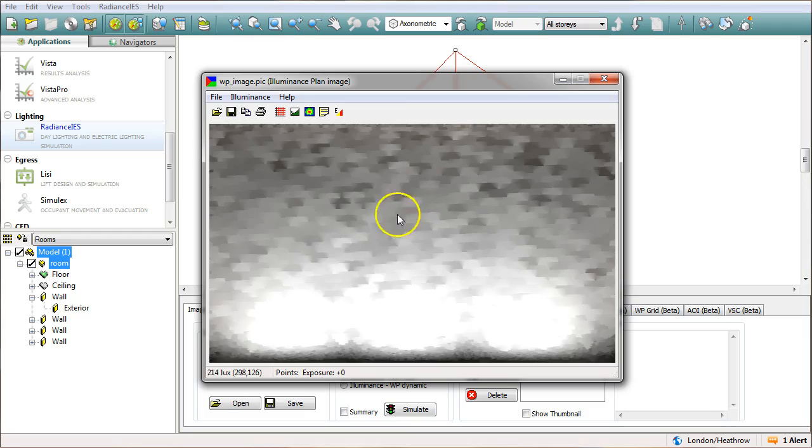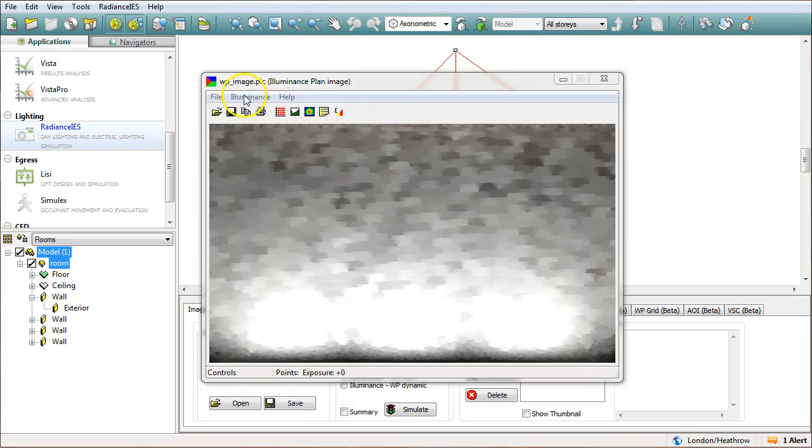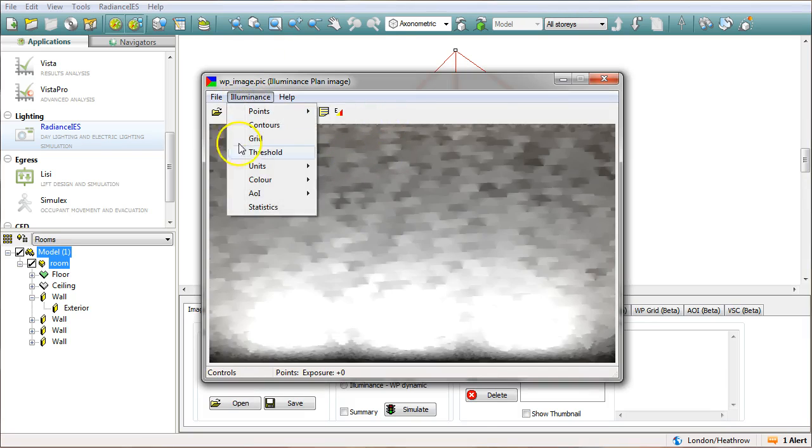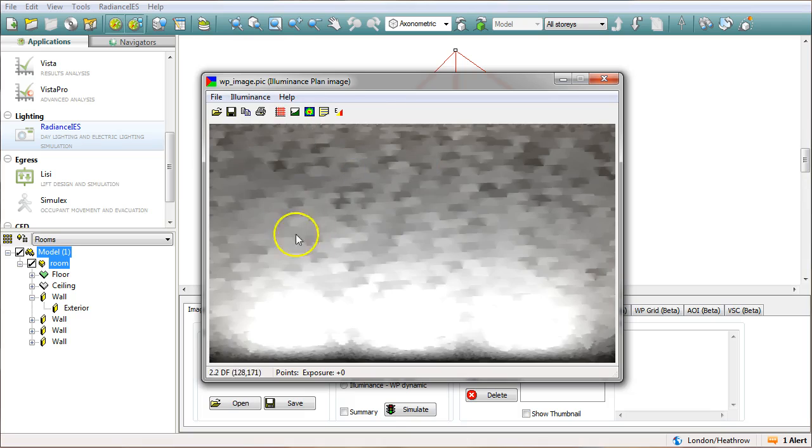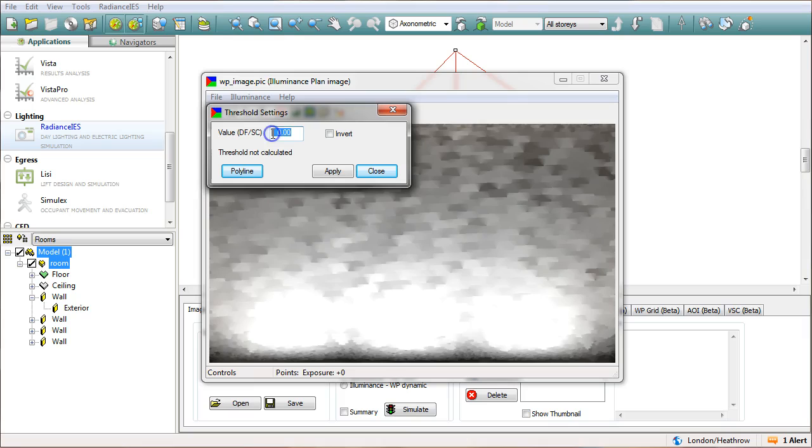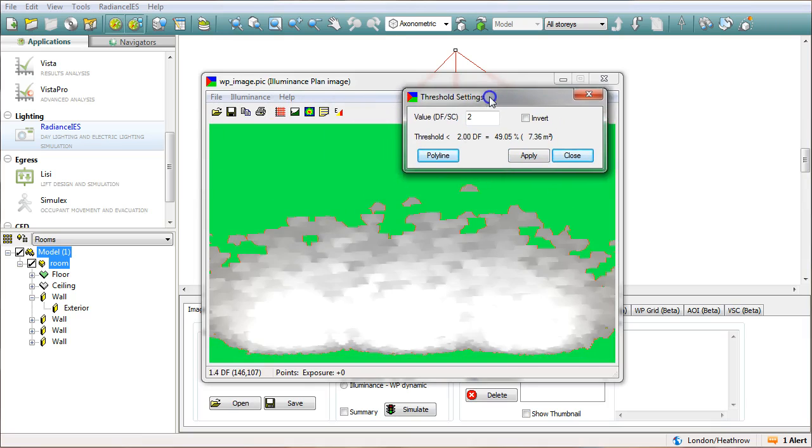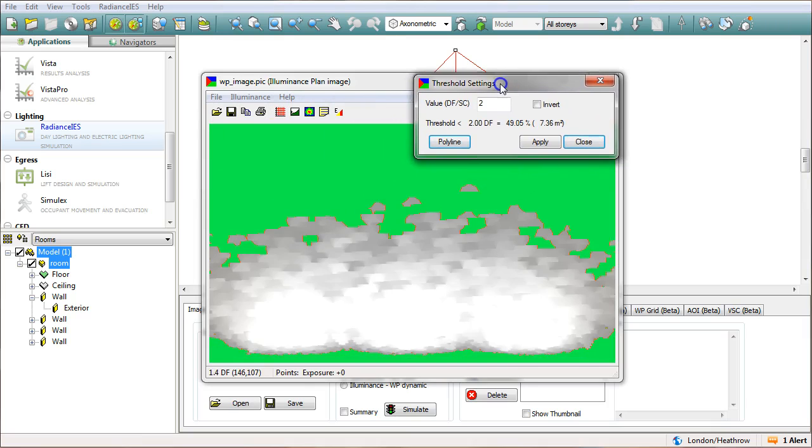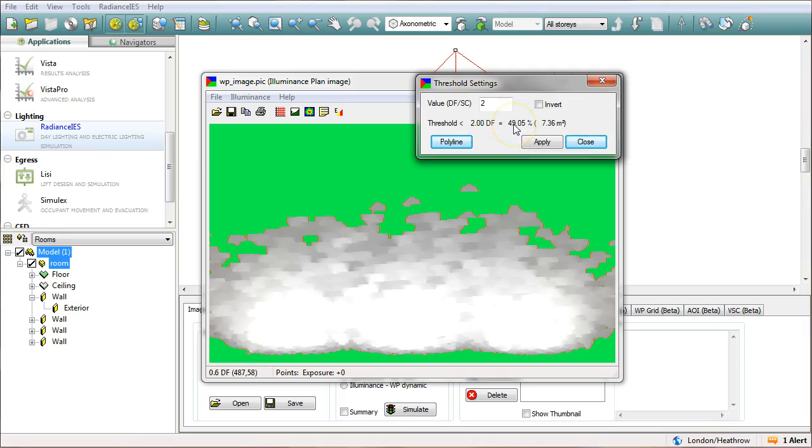Okay so here we have a map of the room and as you can see it's quite blotchy because of the quality being set to medium. Now what I'm going to do here is I'm going to set my units to daylight factor and I'm going to have a look at some thresholds. I'll set that to daylight factor of two and apply and what we have here is a map showing us the areas that have a daylight factor of less than two, so it's 49 percent, pretty much half the room.